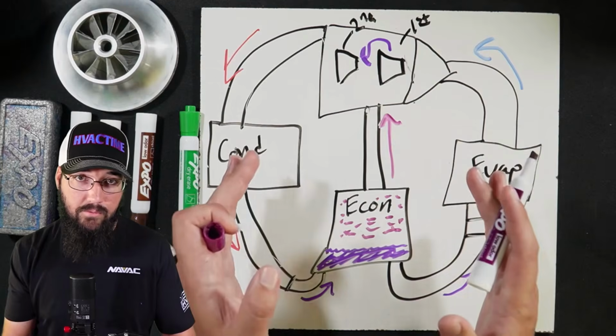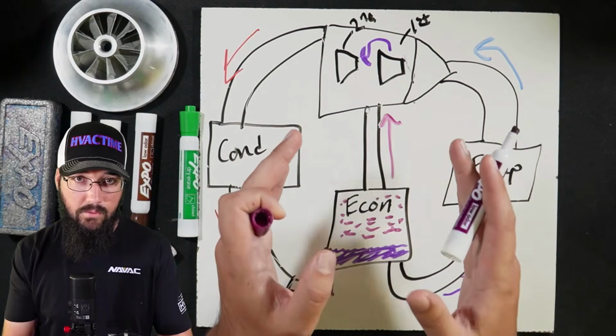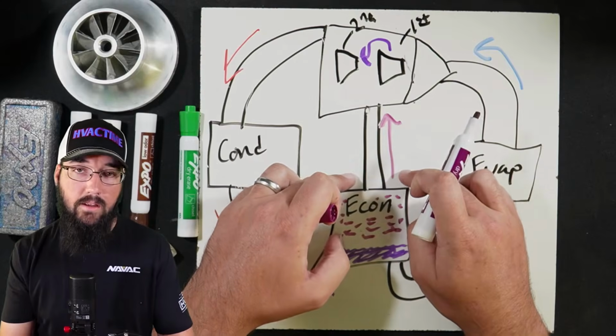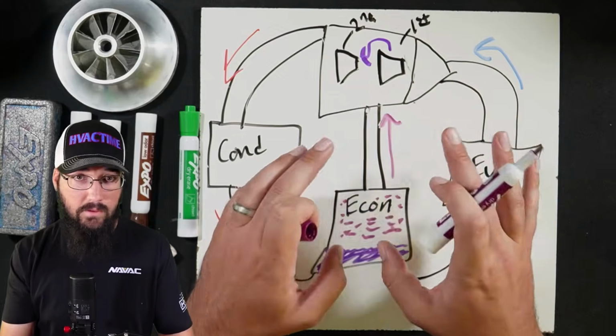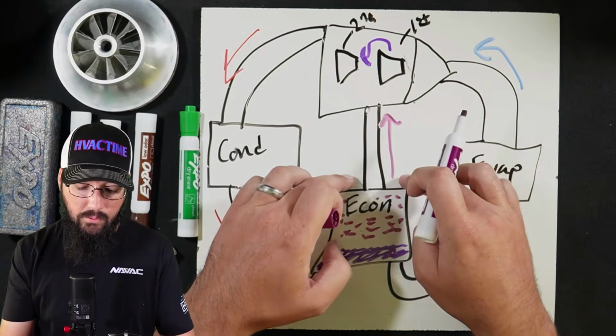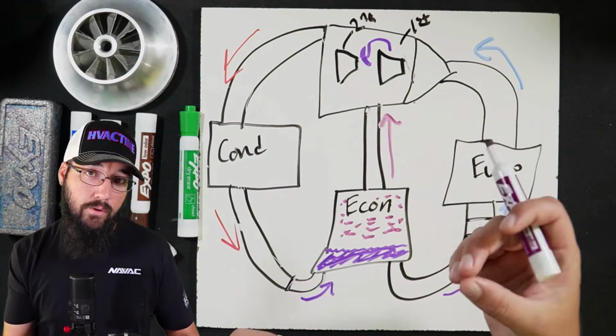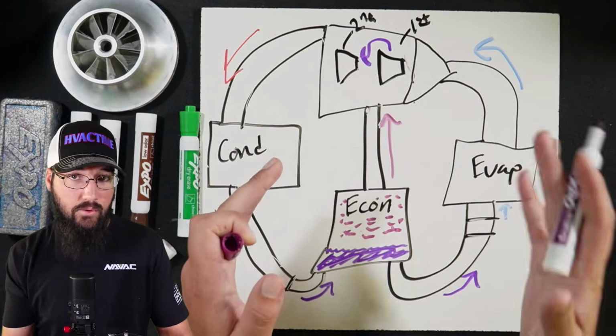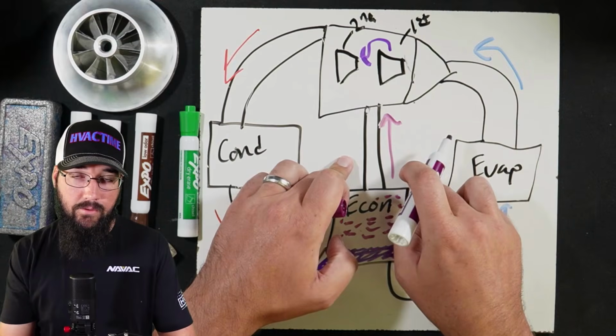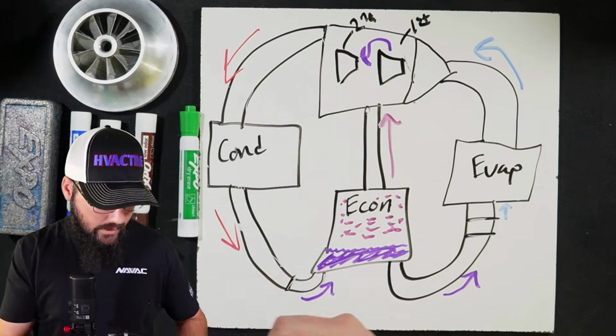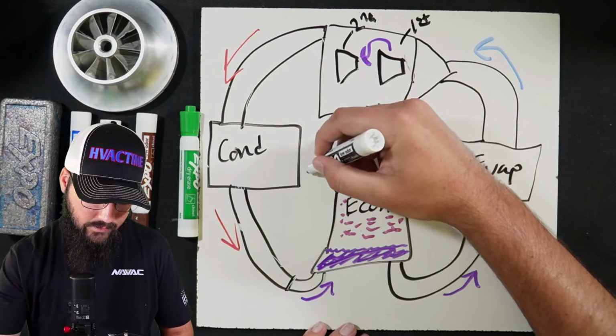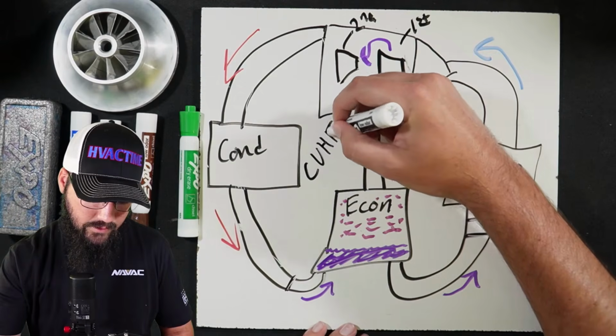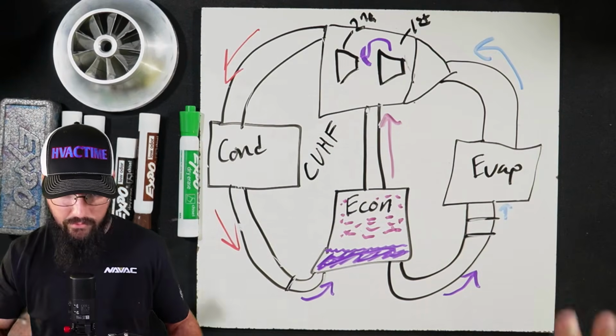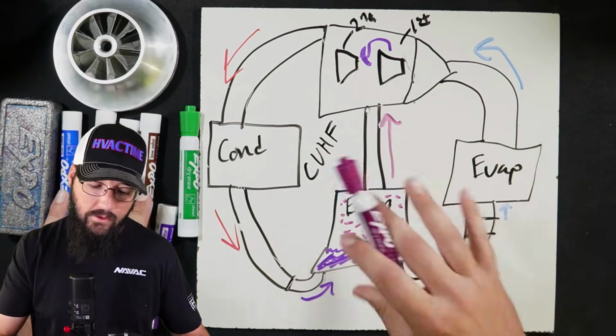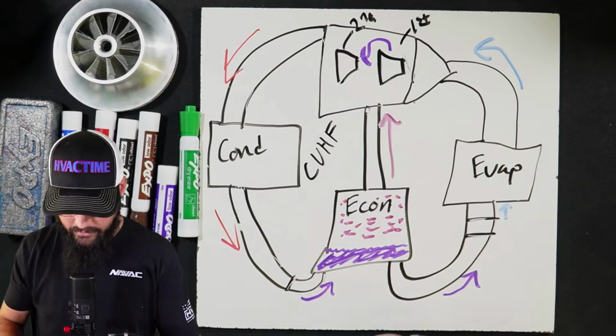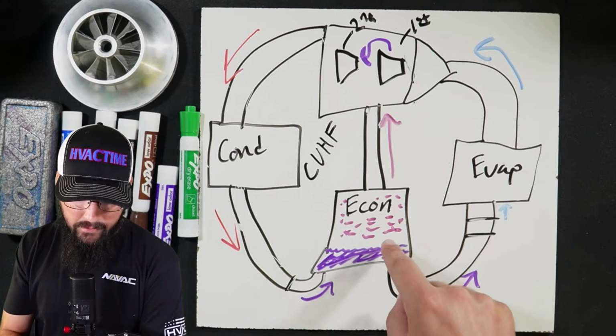Now, not trying to confuse this, but just for clarity, if this was a three-stage machine, you would see two pipes up here. Being that this is only a two-stage compressor with a CVHF, which is our example, you will see just one pipe. And that's one really quick way to determine on these chillers: do I have a three-stage compressor or a two-stage compressor? How many pipes are on the economizer? That will immediately tell you what you need to know. And just in case it helps, we're going to say CVHF, just so that we're fully on the same page. This gets confusing really quickly if we're not careful, so I want to be very cautious of that. Okay, so what happens from here?